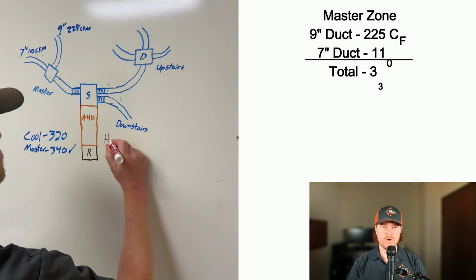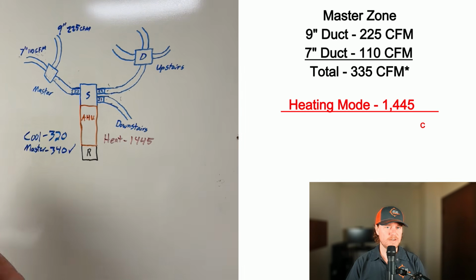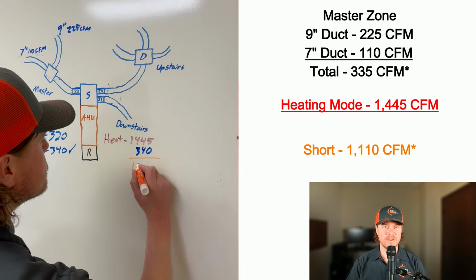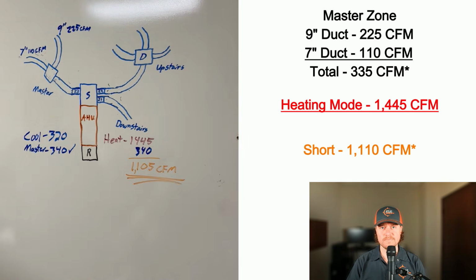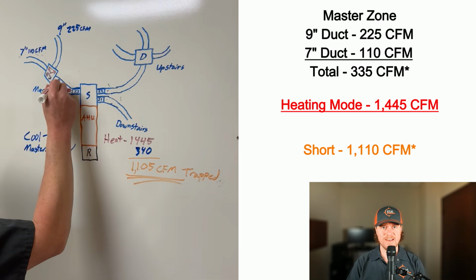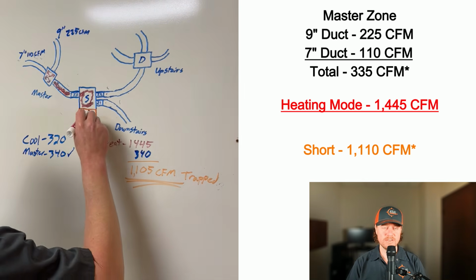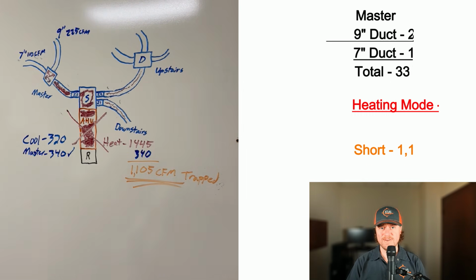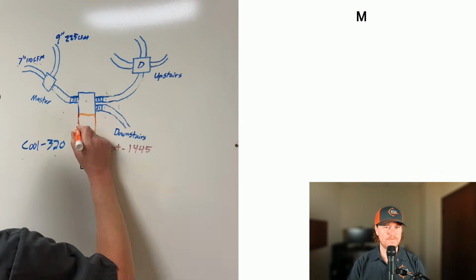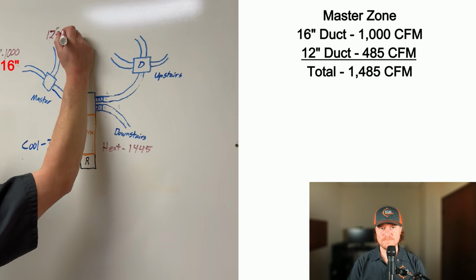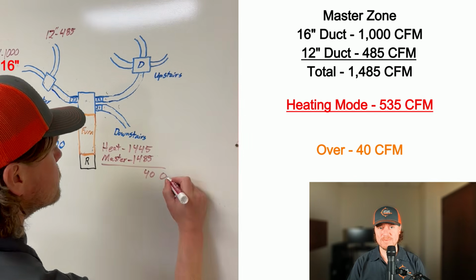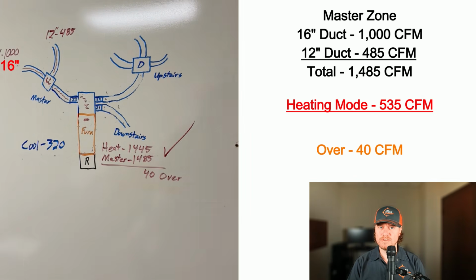If I have this one zone call in heating mode, it's going to try to push 1,400 CFM of heating. It will end up bleeding some of that airflow to the other zones. However, a lot of times not enough. That means a lot of this hot air stays in the cabinet and will trigger the limit switch and turn off the unit. Now, you don't have heating. There's two ways to solve this problem. The first way is to make sure each zone has roughly 3 to 3.5 tons of airflow, which ends up being a ridiculous amount of ductwork, or you can use a different furnace.